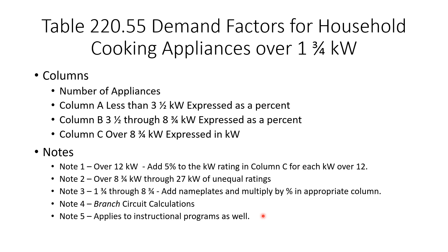Note 5 is straightforward: this table also applies to instructional programs. If it's in a home ec class or similar instructional institution, it's calculated exactly the same as a dwelling. You don't go to the 'other than dwelling' section — an instructional setting is figured the same as a dwelling.